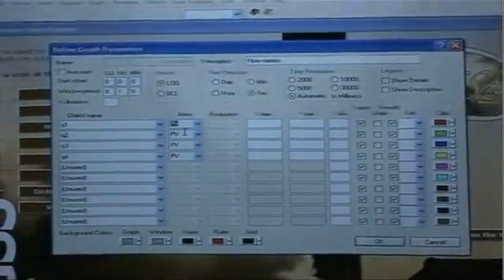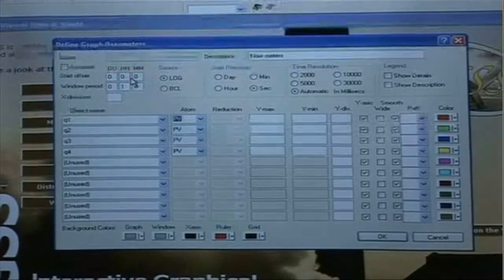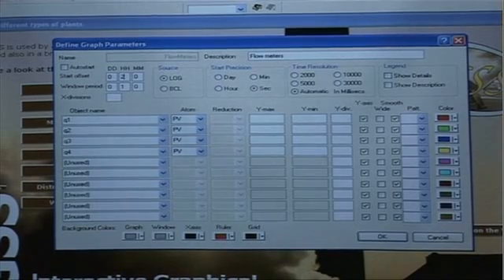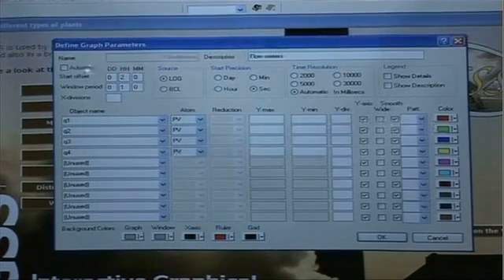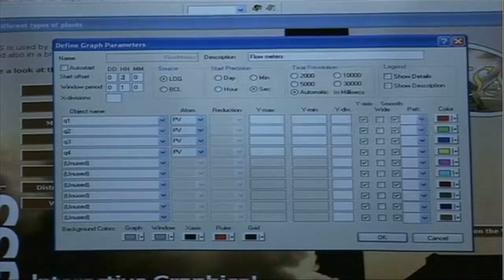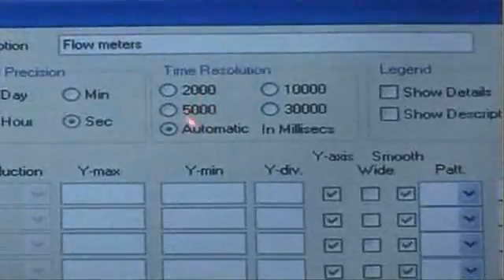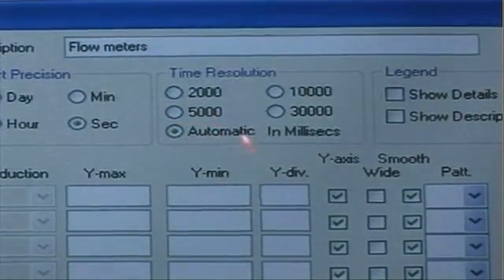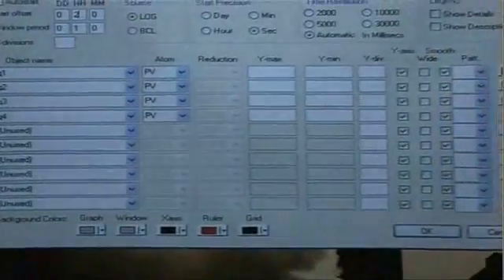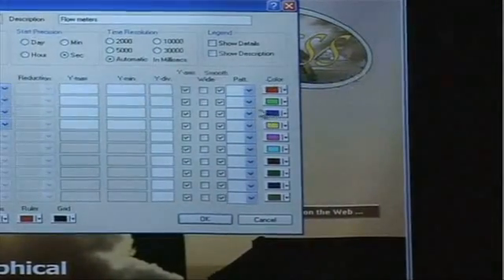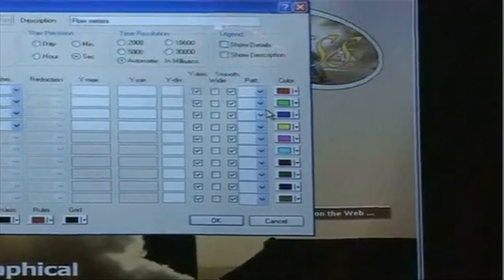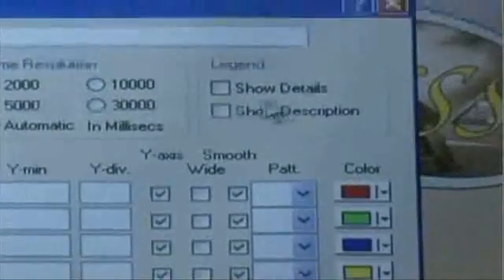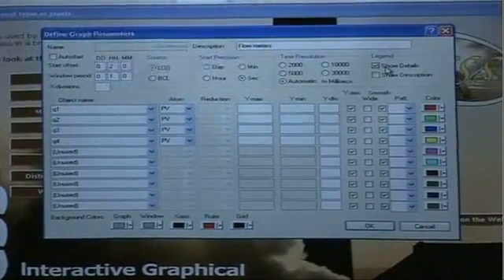When I define a graph in IGSS I can also define a start offset. So if I put in, let's say I put in two hours here, HH for hours, then it means that when I start this graph as an operator it will automatically suggest that I go two hours back and continue from that period. Over here on the right side you can see that the time resolution is set to automatic. It means that it will take the lowest time resolution or lowest scan interval of the objects present in the graph. Also you can see that each object here is assigned a unique color. You can of course change these if you want to. And finally we are also allowed to put on a legend for our graph. We can show details, which means that we will in this case for analog objects also get the measurement scale for these four analog objects that we see here.